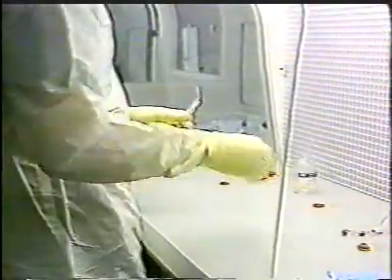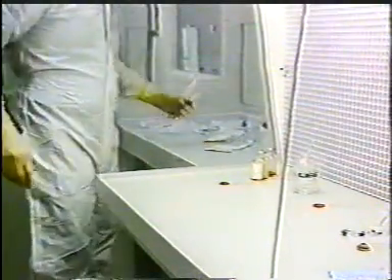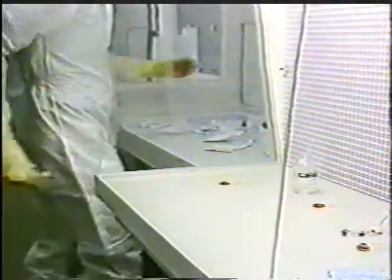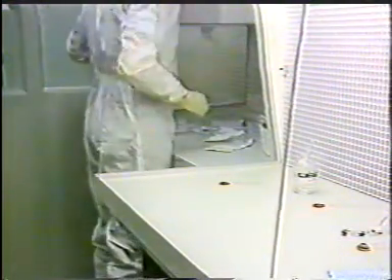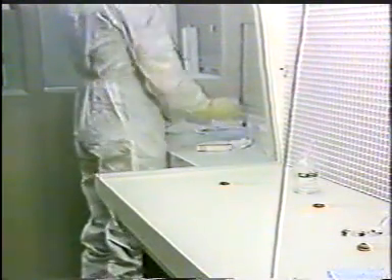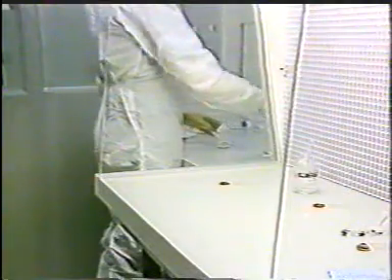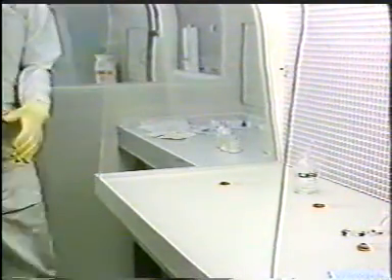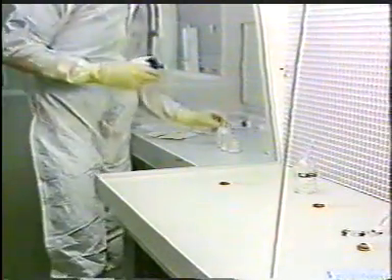Environments are divided into 4 classes, in British Standard 5295, according to the number of airborne particles of various size. Aseptic rooms must meet the standard of the highest class of environment, Class 1. Rooms in which heat sterilised products are prepared and filled must meet the standard for Class 2. These classes are based on the room in an unmanned state.